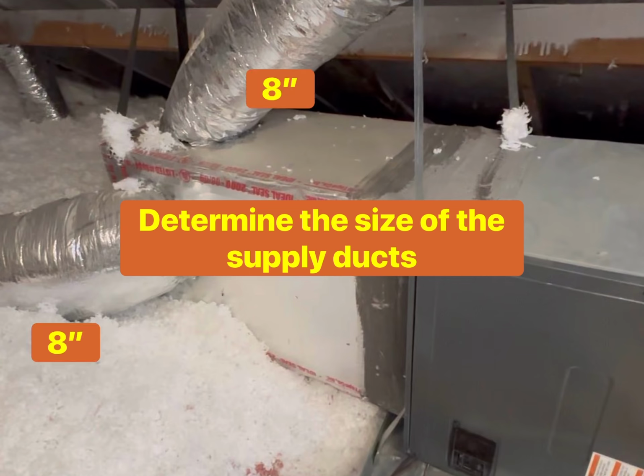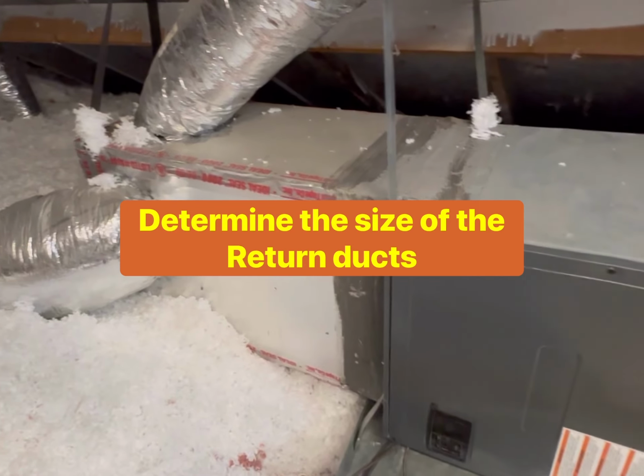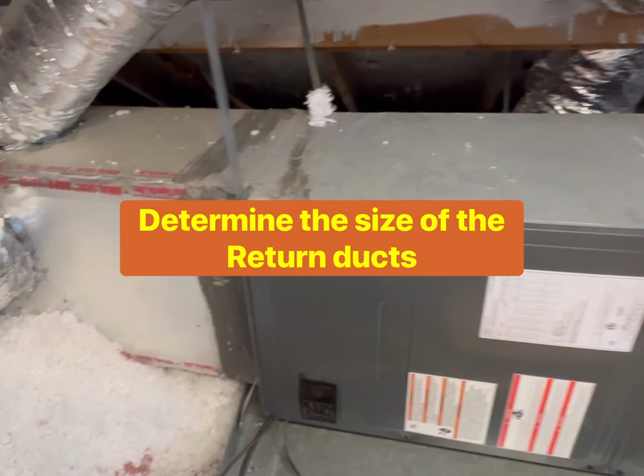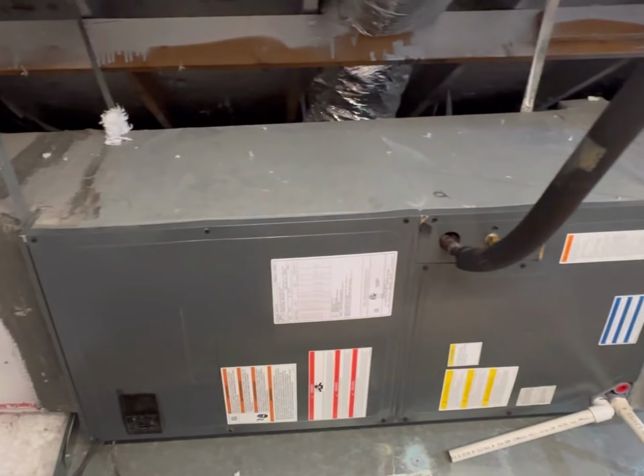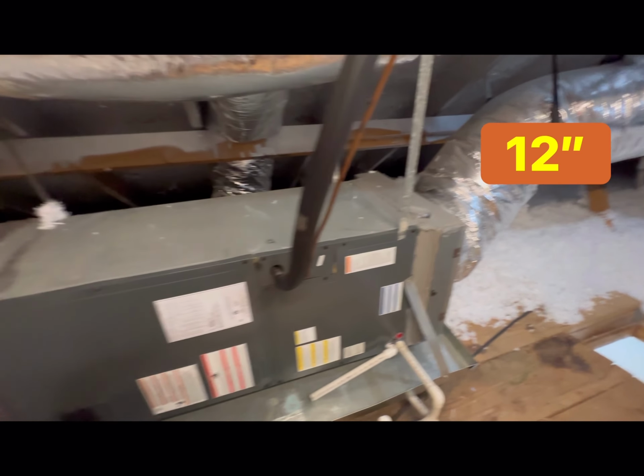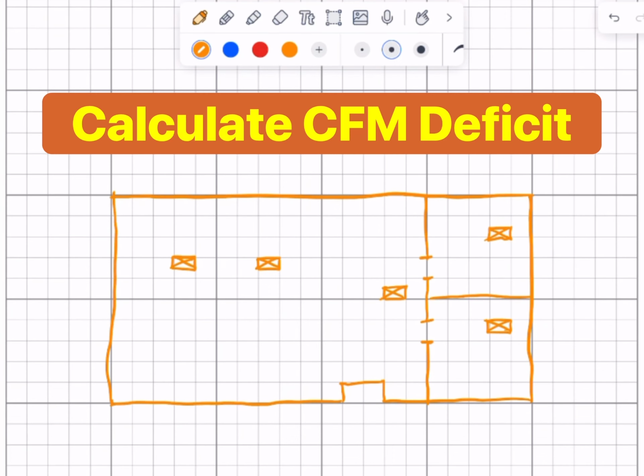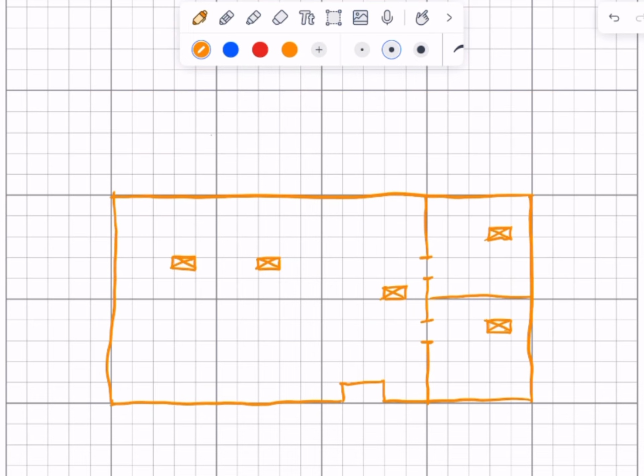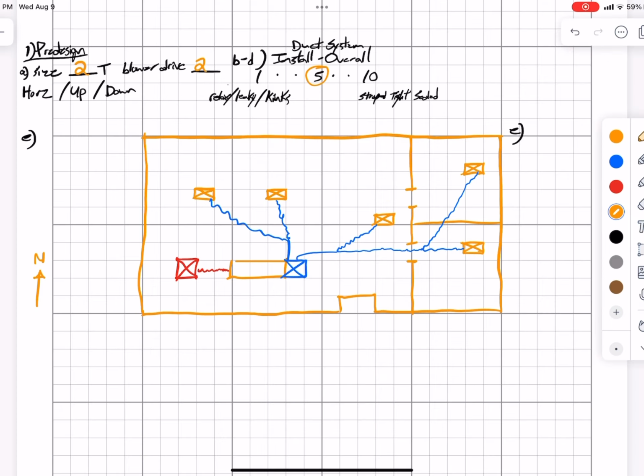There's 2 8-inches in this case. Then we want to determine the size of our return ducts. In this case, there's a single 12-inch. Now it is time to calculate our CFM deficit. Draw a sketch of the home, draw all of the supply registers, and all of the return registers.